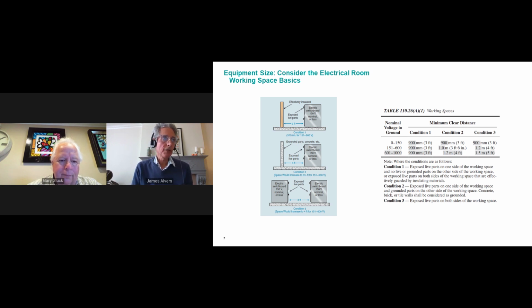This slide here is just some very basic information on electrical room workspace issues. The part of the code that deals with this is 110, Requirements for Electrical Installations, Part 2. It's worth reading that whole section. I'm going to highlight just a few things. Basically, the working space requirement, and there's also a dedicated space requirement. So the code has a table, 110.26, which defines the working space requirement for both the standard 120/208 or 277/480 boards.